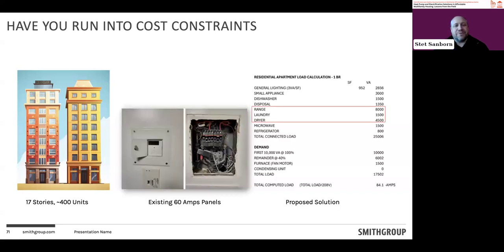So one of the big challenges with existing buildings, especially at the unit level, inside the apartment, is the electrical capacity of the apartment. Oftentimes the building itself might have a capacity issue, but definitely if you're touching inside a unit, we're likely going to run into challenges on panel sizing. In this particular project, each apartment had its own load center that was only 60 amps. Now 60 amps isn't undersized at all for a load center. It is for new construction, but for an existing building, we could certainly come up with something.